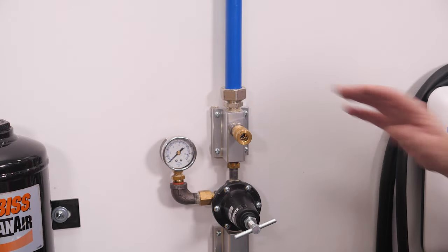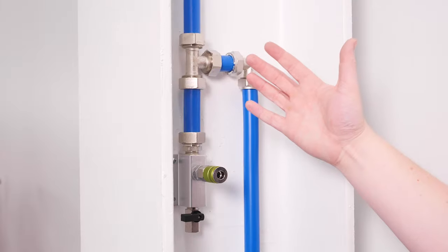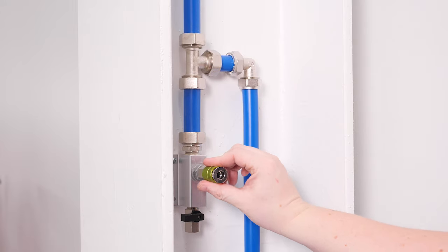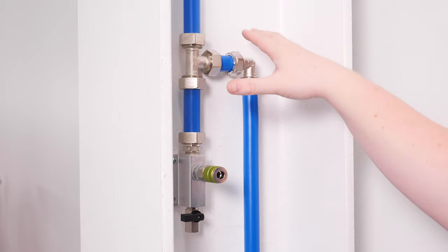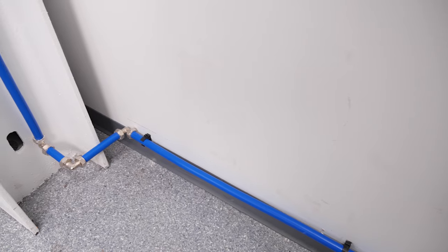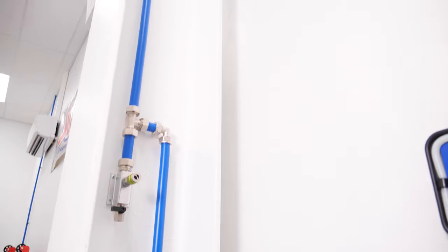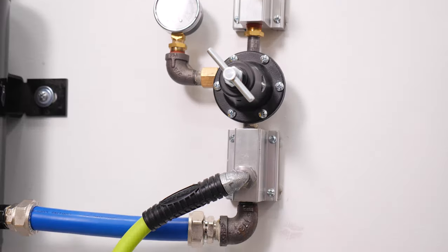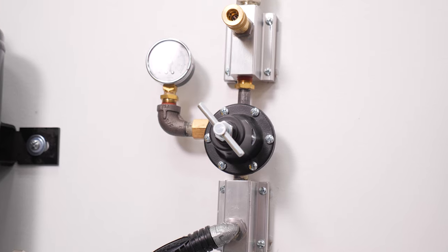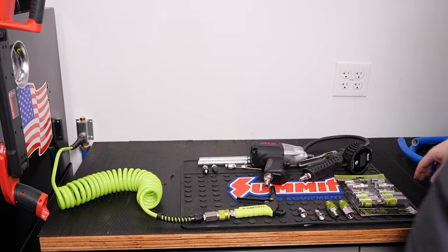Once all the fittings are connected, pressure-check them with soapy water to make sure they're not leaking. Here's our second air drop — just another aluminum block and a quick connect fitting. When installing your MaxLine system, if you're not using 90-degree fittings, use long swooping bends — you don't want to kink the tubing. Since we didn't have much room here, we installed a couple of 90s to tuck it in. The system runs in series, so this connection is after the regulator and the air pressure here is regulated.